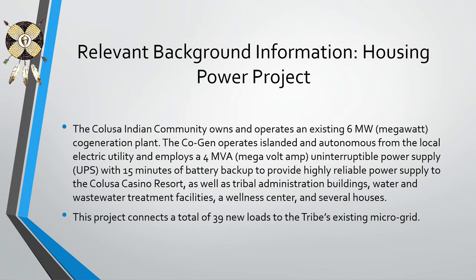This is some relevant background info on each of the projects. The tribe owns and operates an existing 6 megawatt cogen plant. This plant operates islanded and autonomous from PG&E, meaning we generate 100% of our own electricity. We do have the ability to parallel connect, but very rarely do. We've had a single outage in the last 9 years, which is a pretty remarkable feat. We employ a 4 megavolt amp UPS system with 15 minutes of battery backup that provides highly reliable power to the resort as well as all the other loads the tribe has.